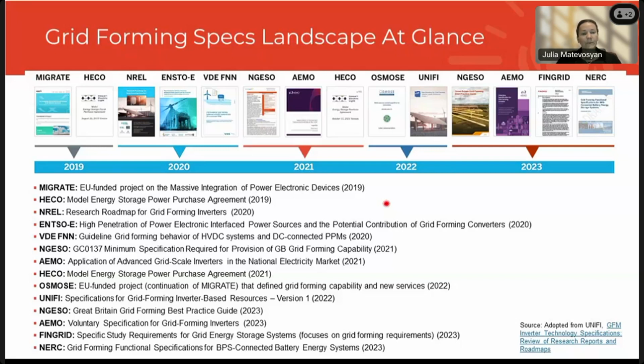AEMO then followed with a kind of white paper showing interest of AEMO in inverters with advanced capabilities, and they plan going forward with deploying those. HECO then followed with more detailed requirements for grid forming batteries going forward. And so this time they had a little bit more specificity in the power purchase agreement, but also there was an additional document that describes tests, simulation tests that should be applied to a validated model representative of a grid forming battery plant. And these tests would prove its grid forming capability. So that was the idea.